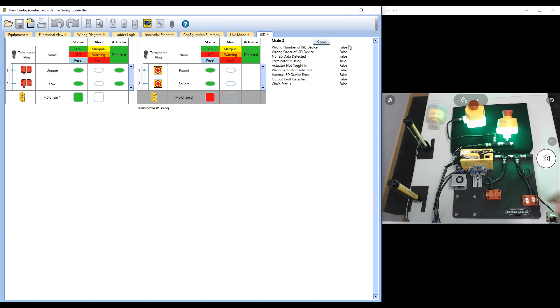It can also tell you if you have the wrong number of devices. If you expected 3 RFID switches and there are only 2 because someone removed one, we'll send that alert to the PLC. If you have the wrong order, like planning an E-stop, then a door switch, then an E-stop, but it sees all E-stops instead, it'll detect that something's incorrect. If an actuator, like in the uniquely coded system, isn't taught, we'll alert you to go teach door number 3.